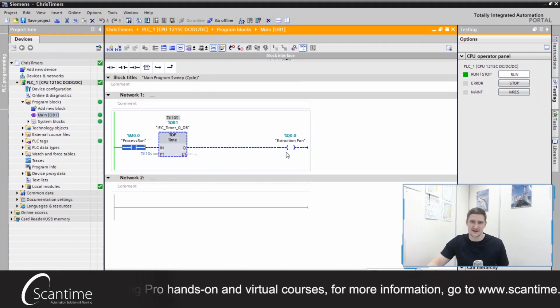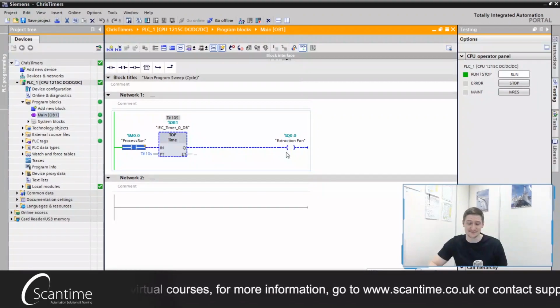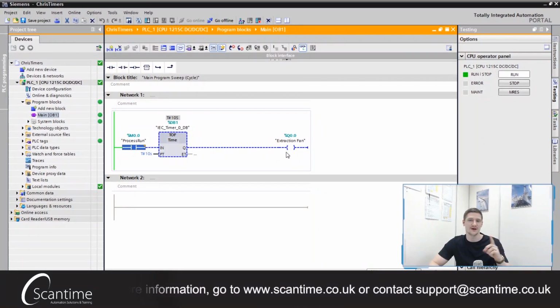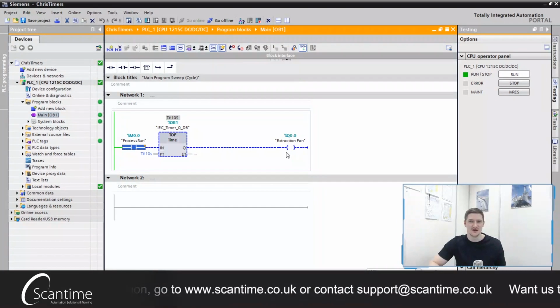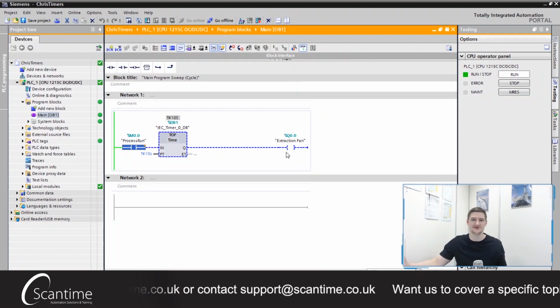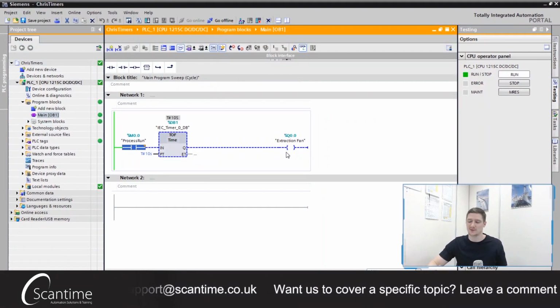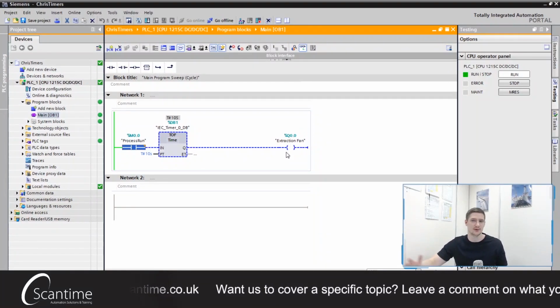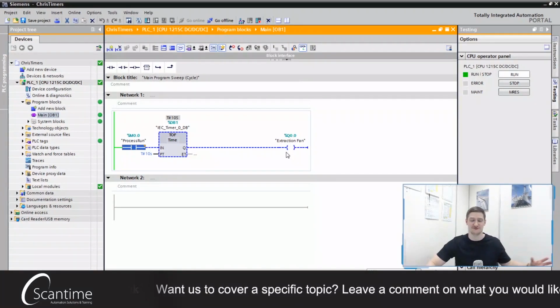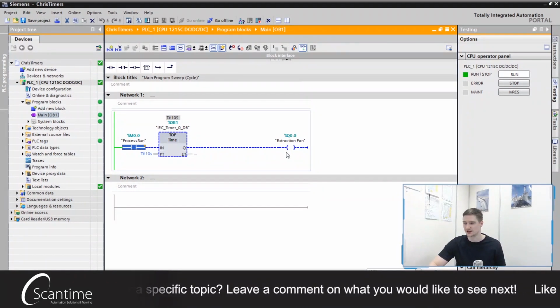However, in other PLCs, for example, Mitsubishi GX Developer on the older PLCs, we only had one timer. And that was our TON timer. The TON timer is probably the most popular timer in all PLCs. Every PLC has them. If you go to Mitsubishi PLCs, however, they might not have the timer pulse. They might not have the TOF timer, depending upon the age of the PLC or what PLC you're working with.